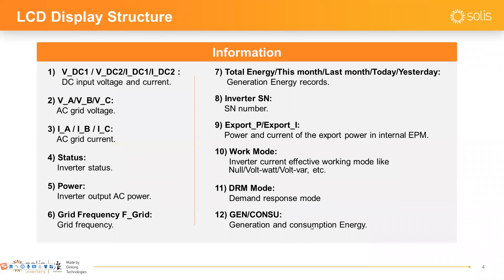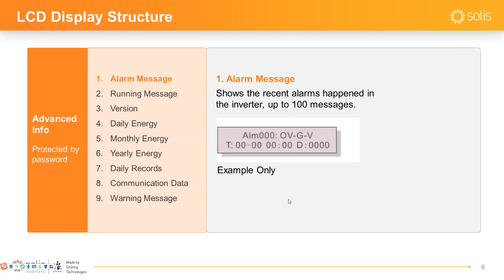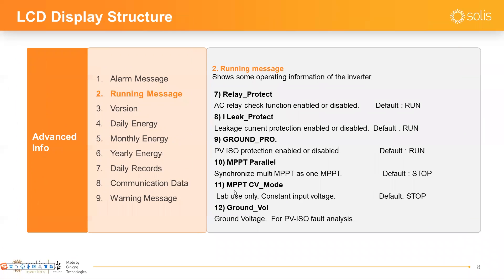Generation and Consumption: if you have a meter connected to the inverter, it can record consumption and generation data. MPPT CV Mode is also lab-use only — the MPPT tracks a fixed voltage point rather than following the IV curve. Not useful in real installations, so just leave it.